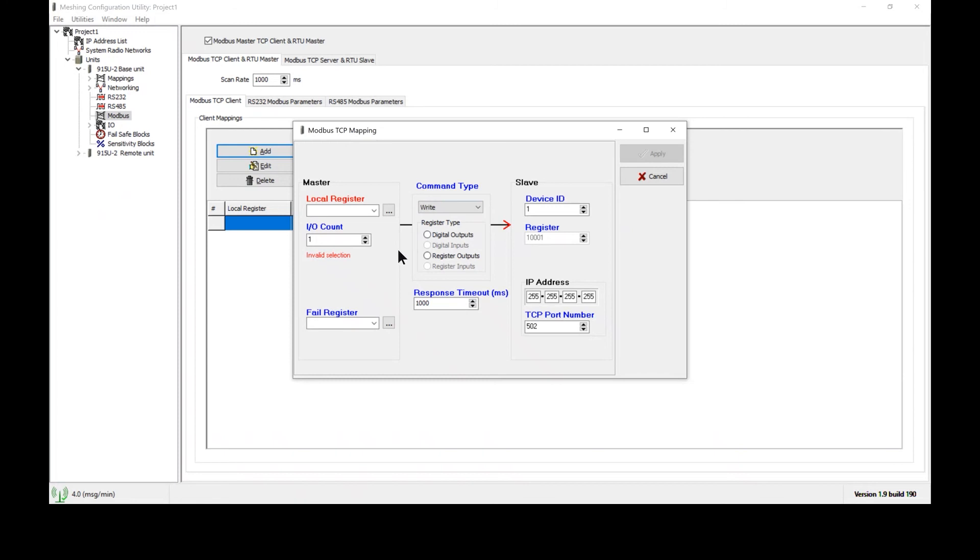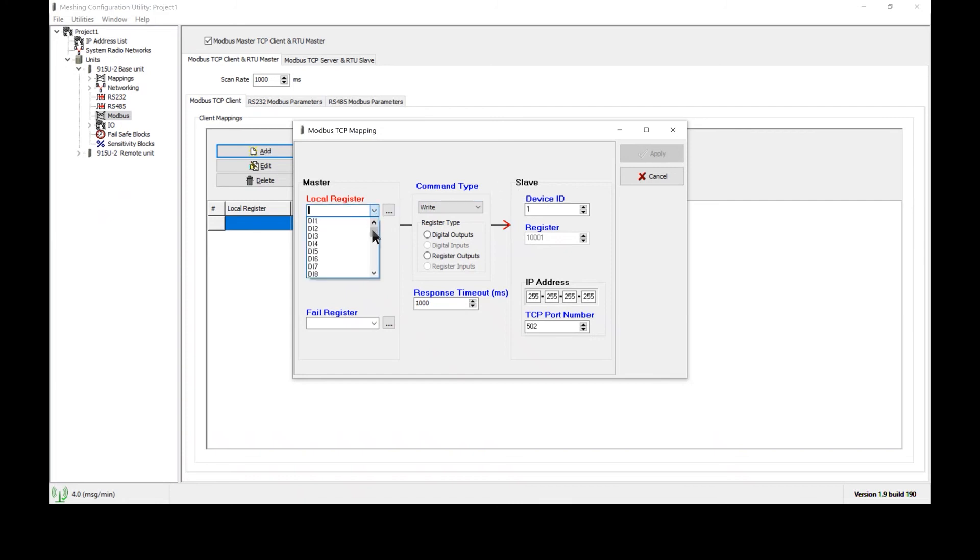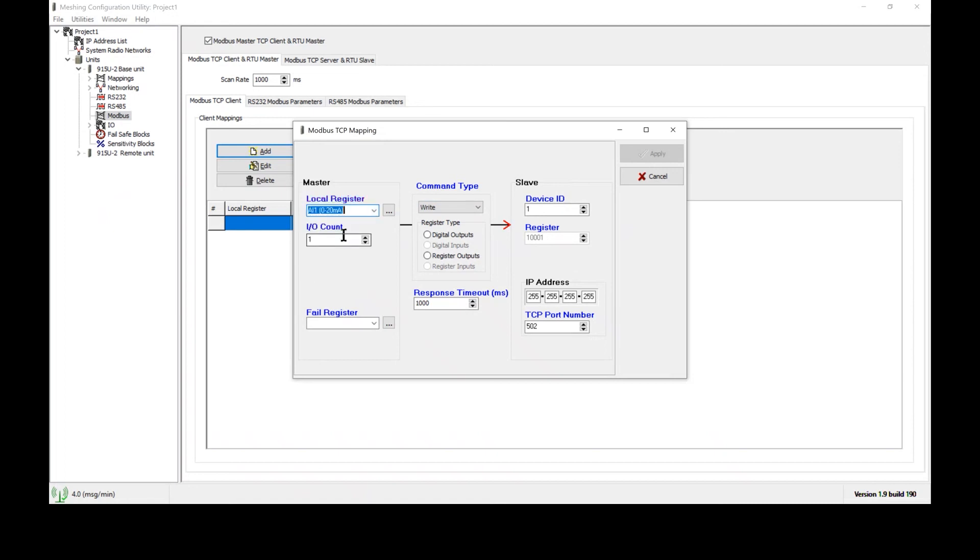The command type just determines what direction the data will flow. In this case let's assume we want to take Analog Inputs 1 and 2 and send them into this PLC which is connected to this radio's Ethernet port. What we would do is we would select the Analog Inputs from the list. I'll select Analog Input 1, select a count of 2 and since these are consecutive registers that means Analog Inputs 1 and 2 will be sent over.